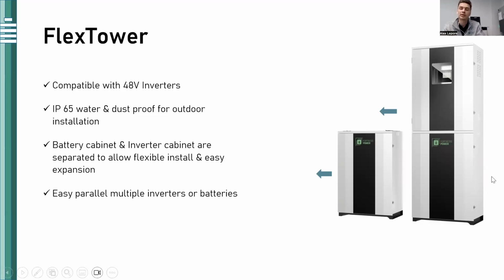So what Fortress did was say, okay, we have an outdoor rated battery, an outdoor rated inverter, in an outdoor rated box with venting on the inverter side and passive venting on the battery side. That way, not only can we install it outside to handle the elements, but we can also mitigate the temperature. In the battery cabinet itself, there's a DIN rail.